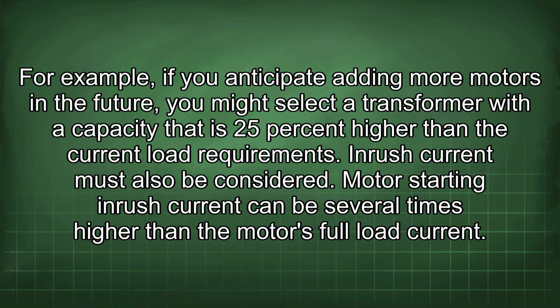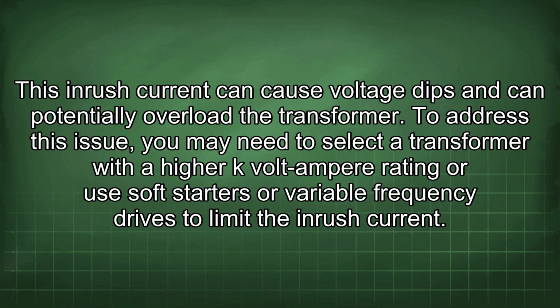Inrush current must also be considered. Motor starting inrush current can be several times higher than the motor's full load current. This inrush current can cause voltage dips and can potentially overload the transformer. To address this issue, you may need to select a transformer with a higher kVA rating or use soft starters or variable frequency drives to limit the inrush current.